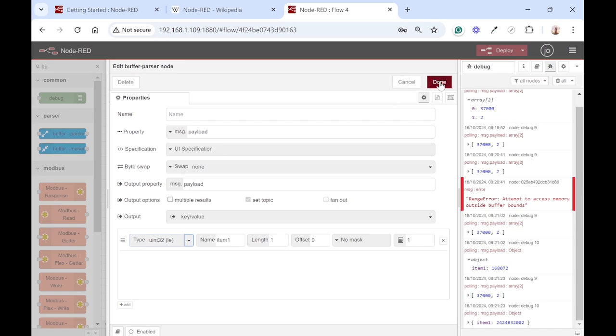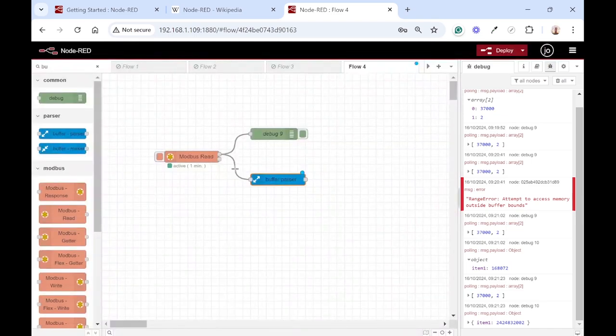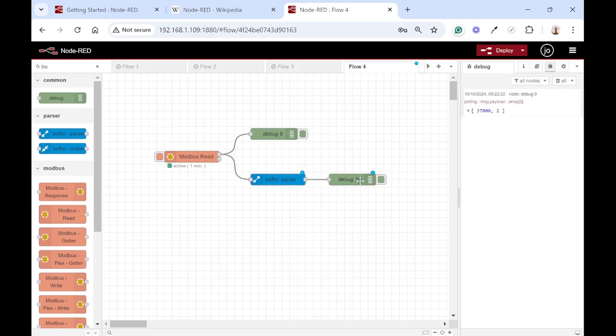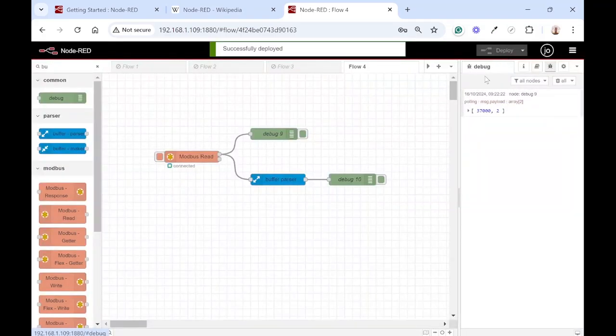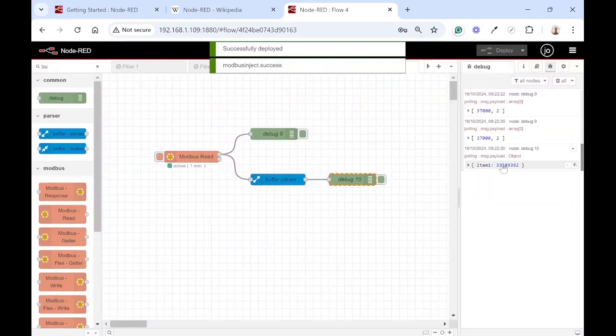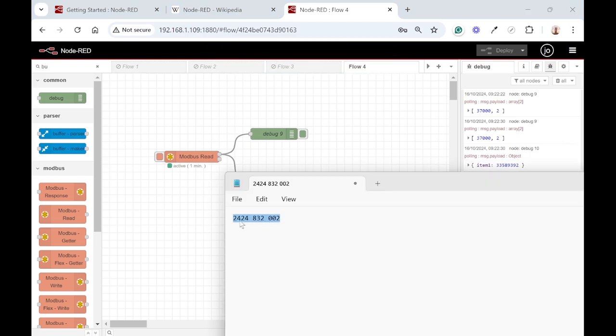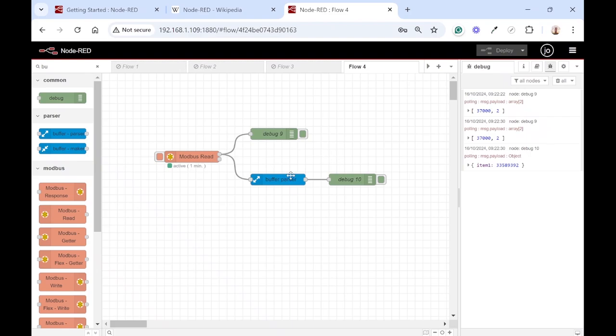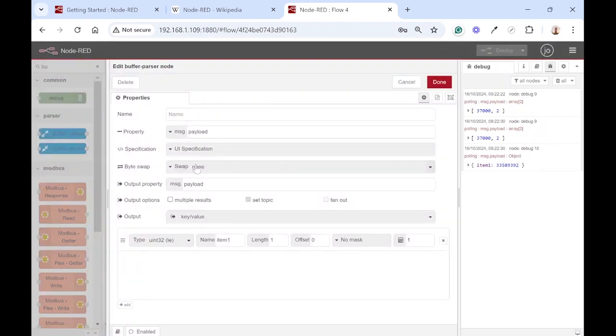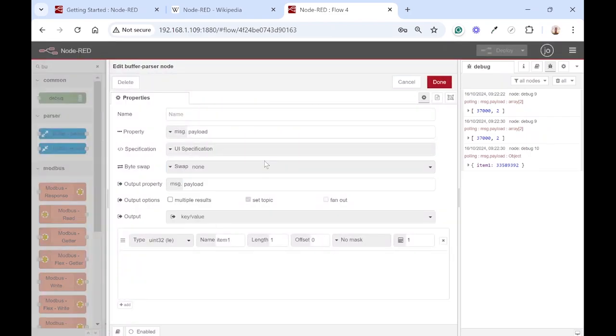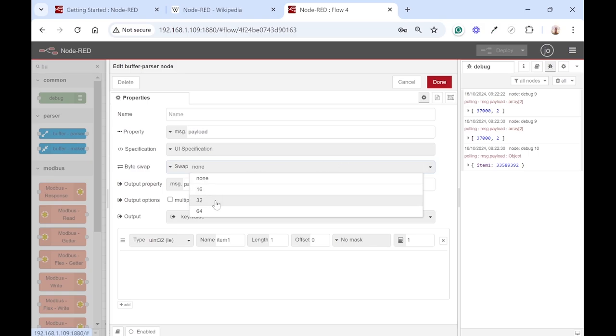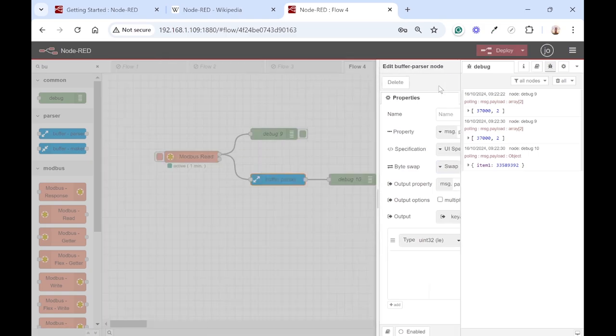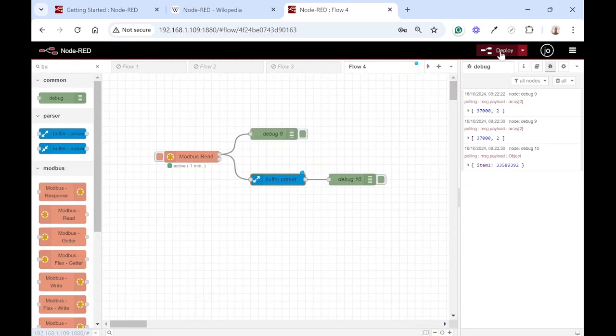If we click done and clear all the debug info, then add another debug node and wire it up and deploy. Let's see what we're getting there. We're getting a value back but it's still not what we expected. That's because we still need to swap the bytes. You can just say swap 32, done, and deploy.